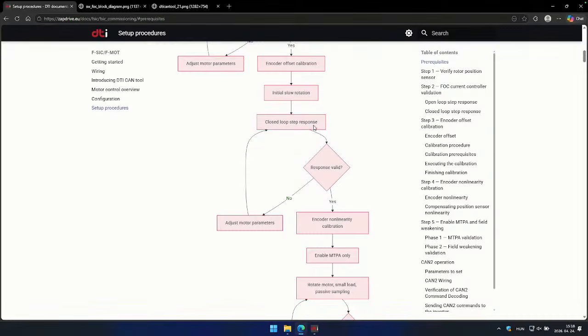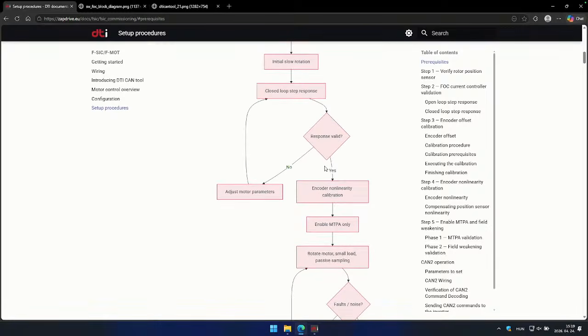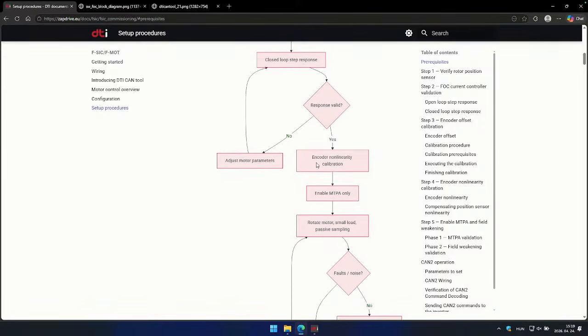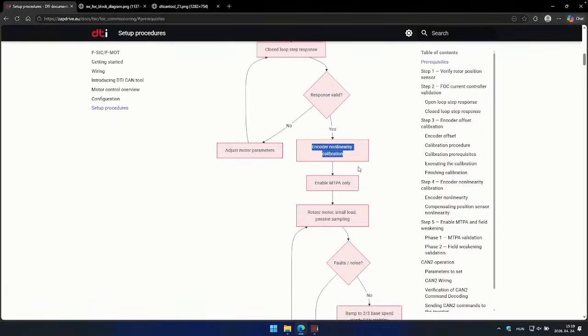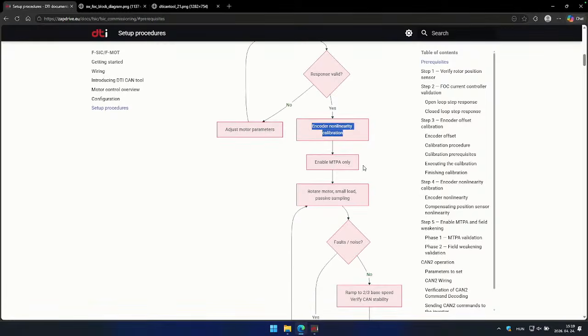Next one is the closed loop step response. It means that we will spin the motor from an external source. We are commanding via the CAN2 interface. We are giving some target like 5 amps or 10 amps, and we will do an active sampling, injecting 10 amps, and we will observe the output to see if the current controller performs well when the motor is spinning. And when we are done with that and verified, the next one is the encoder nonlinearity calibration.